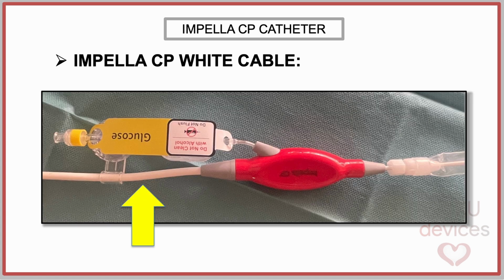The white connector cable or driveline is attached to the proximal end of the red plug. It connects the Impella catheter to the automated Impella controller. Its main role is to transmit the power, optical fiber, and electrical signals that allow the controller to monitor and regulate pump performance. Additionally, it serves as the structural support for the purge system. The cable's design also minimizes electromagnetic interference, maintaining accurate signal transmission and overall system reliability.